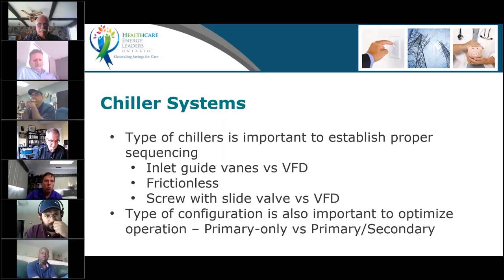Make sure you know what type of chiller you have and what type of loop configuration. I don't want to go too much into technical details, but again, these are things you need to be aware of. There are systems that are called primary only. That means the water goes through your chiller and then through the building with one set of pumps. If you want to go variable flow, you can, but you have to know the limits, the constraints of your chillers. Chillers, like I said, can be finicky machines. They're designed to have a flow of 2.4 gallons per minute per ton of capacity. Most of them, you can take down to about 1.2 gallons per minute in theory. They don't always work properly when you do that.